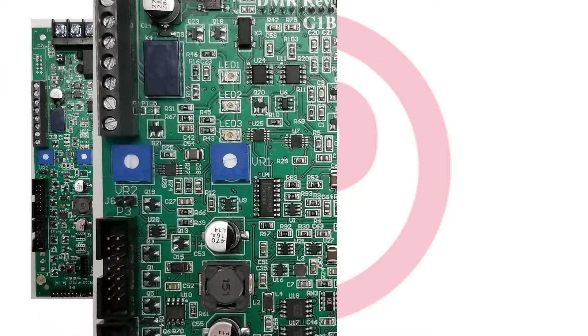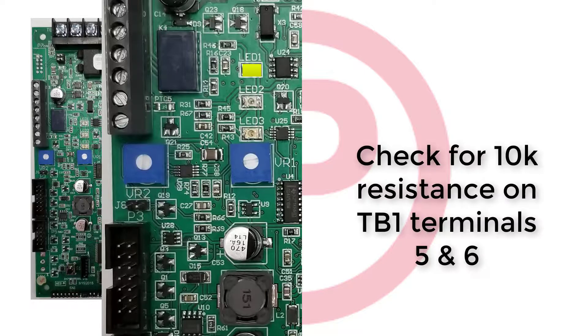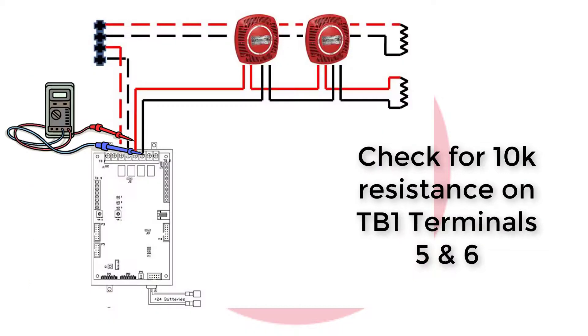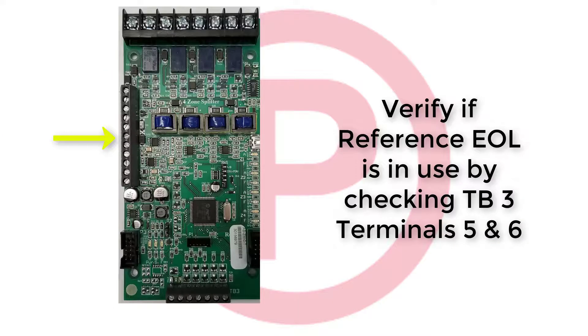If the yellow LED is on and the green LED flashes four times, then a speaker circuit is shorted. Using an ohmmeter, check for 10K of resistance on the speaker circuit wiring, terminal block 1, terminals 5 and 6. If the value is not 10K, verify that a reference end of line resistor is not being used prior to troubleshooting further. If a reference EOL is being utilized, then that value should match the speaker circuit resistance.